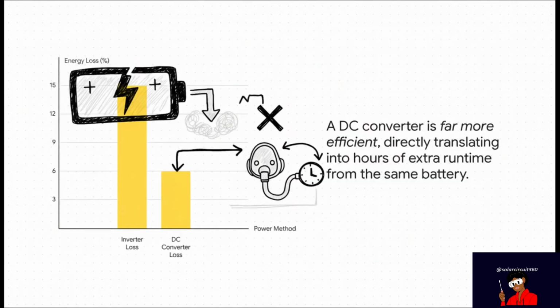And the numbers really tell the story. An inverter is going to waste 10 to 20% of your precious battery power. A good DC converter, the loss is more like 4 to 8%. That difference translates directly into hours of extra runtime from the very same battery.